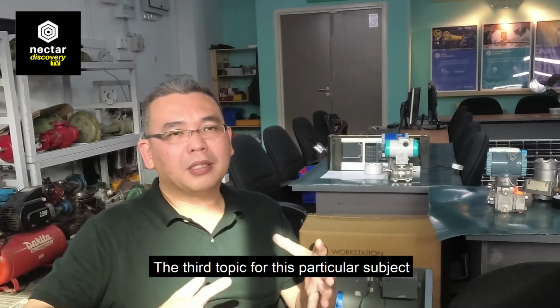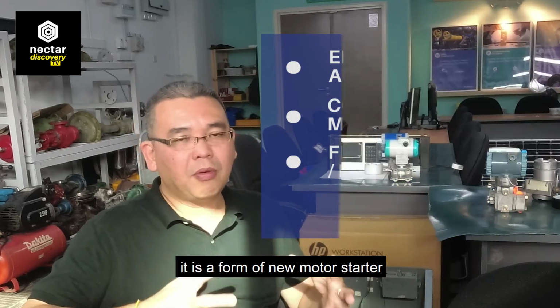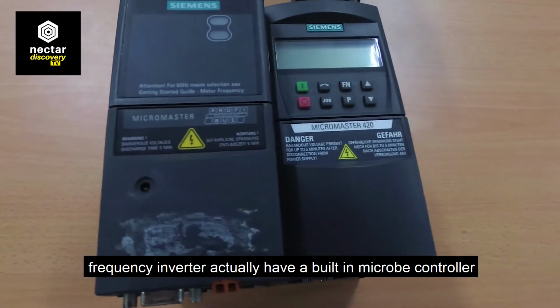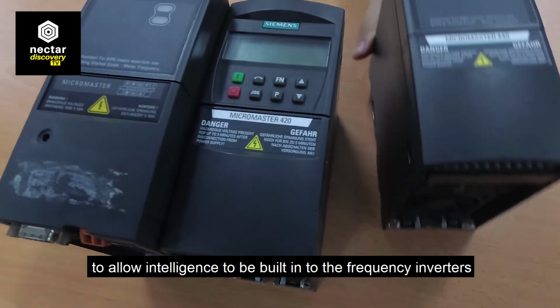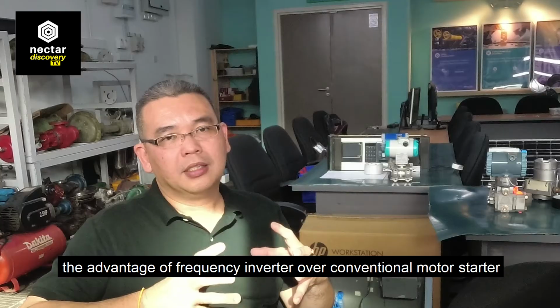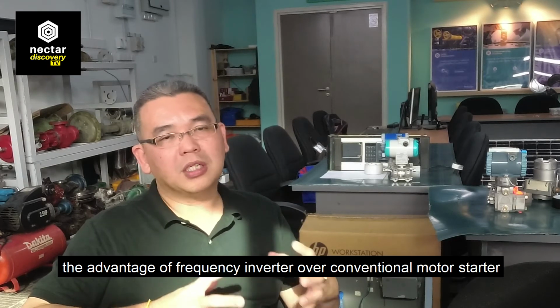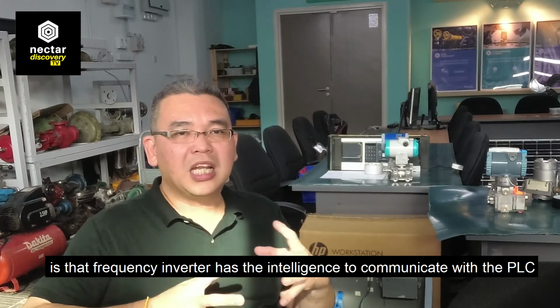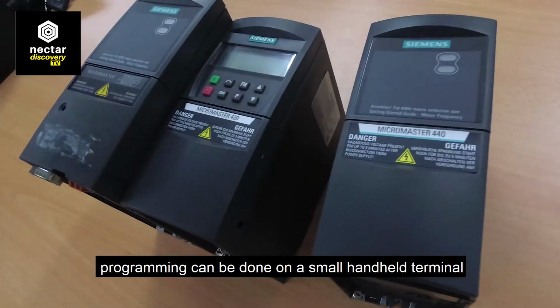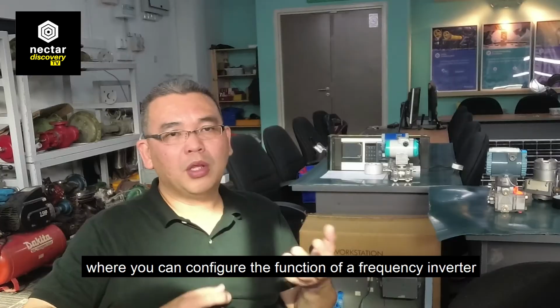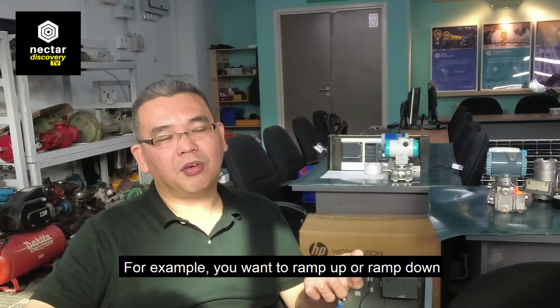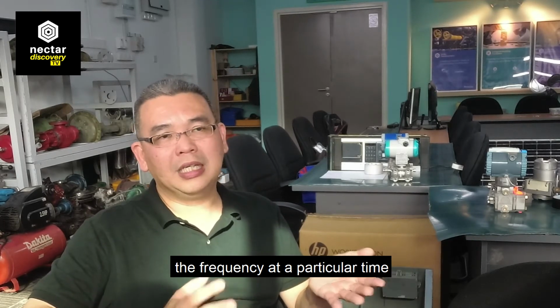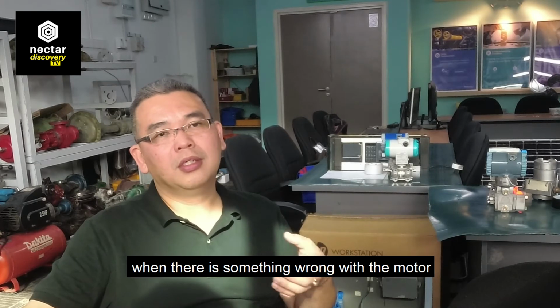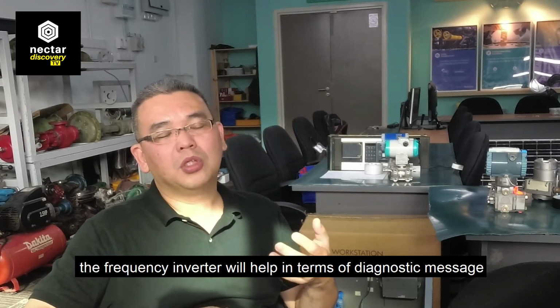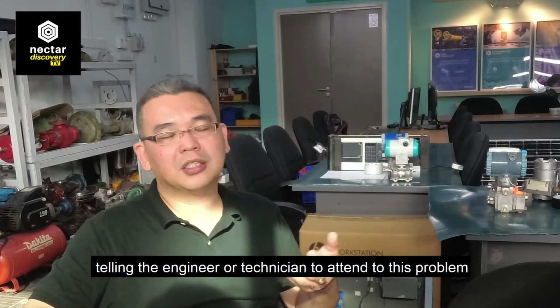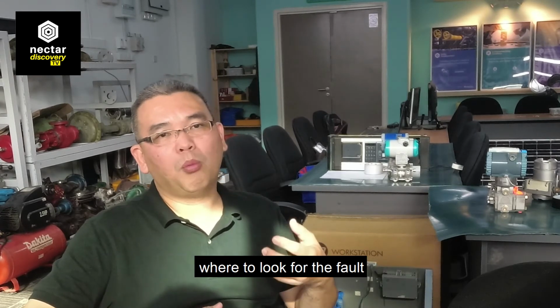The third topic for this particular subject is the frequency inverter, a form of new motor starter. A frequency inverter actually has a built-in microcontroller to allow intelligence to be built into it. The advantage of the frequency inverter over the conventional motor starter is that it has the intelligence to communicate with the PLCs. Programming can be done on a small handheld terminal where you can configure the function of the frequency inverter, for example, if you want to ramp up or ramp down the frequency in a particular time. If something is wrong with the motor, the frequency inverter will help with diagnostic messages telling the engineers or the technician who attends to the problem where to look for the fault.